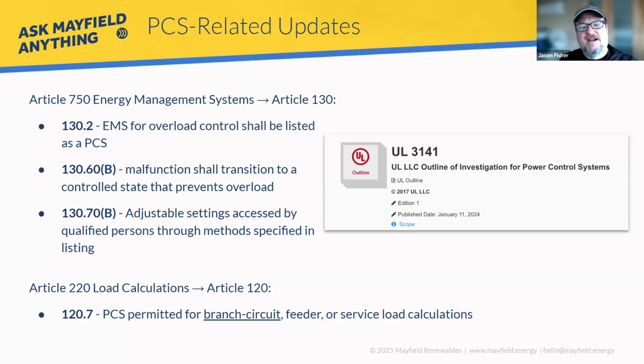So the big warning here is: don't assume that just because somebody says I have this PCS listing or evaluation, I can utilize these special allowances like 120.7 in the 2026 code. They have to actually back that up to show they've been tested and listed for that function — this overload control function. There are multiple functions a PCS can do: zero export, non-import, all these different use cases or modes. But code really cares about whether we're overloading conductors or overloading bus bars.